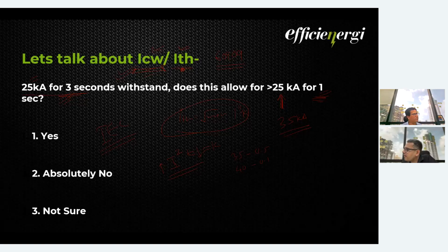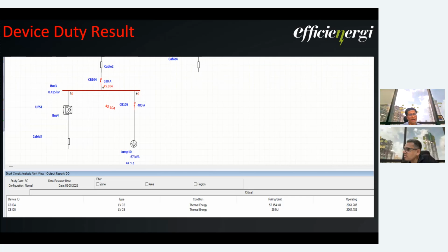Okay, so I think we can now move on. Now again the same graph and the same breaker that we explained earlier. This is the 630 breaker, this is the 400 breaker. We run the device duty, and the result shows the thermal energy. You must have seen in your SCC reports, you open any of your SCC reports, these figures will not be there. The device duty comparison on thermal energy, nobody does or nobody asks for. But basically, you must be asking for this particular device duty compliance.